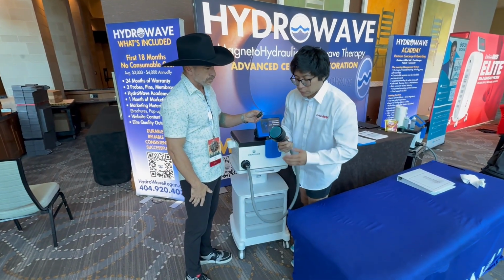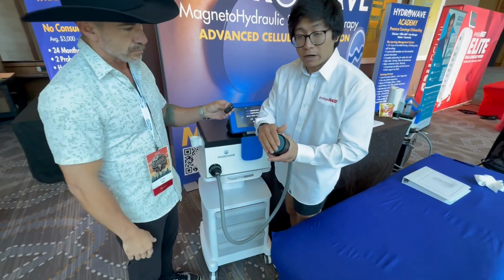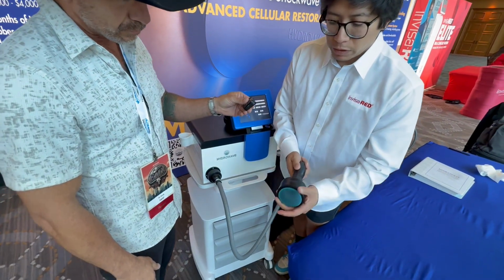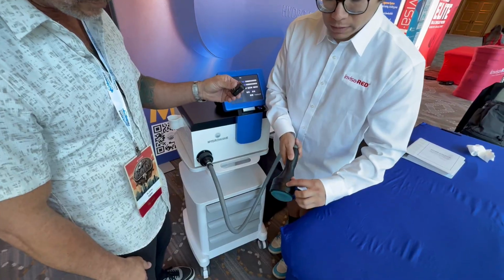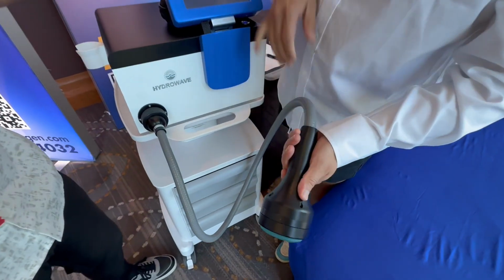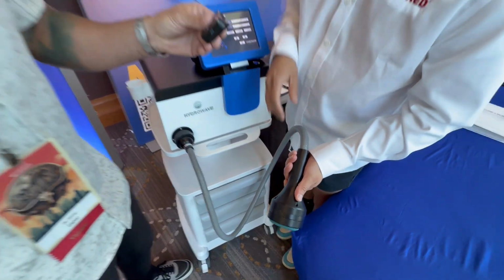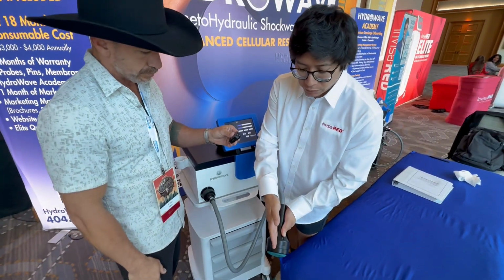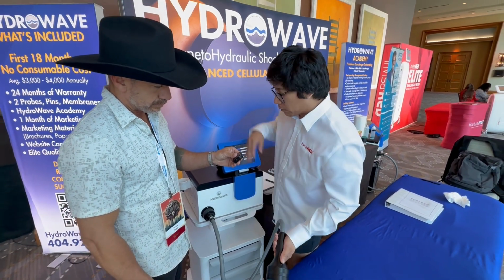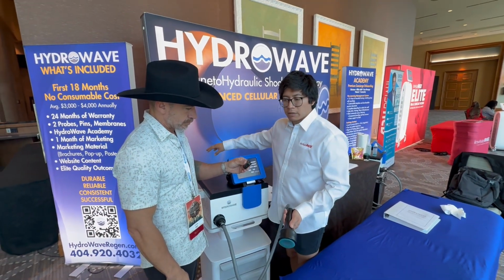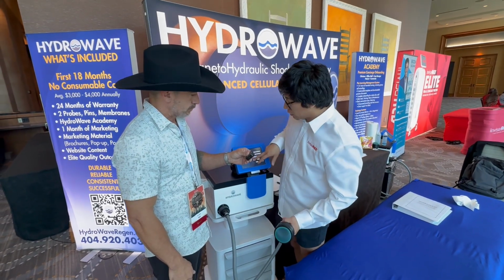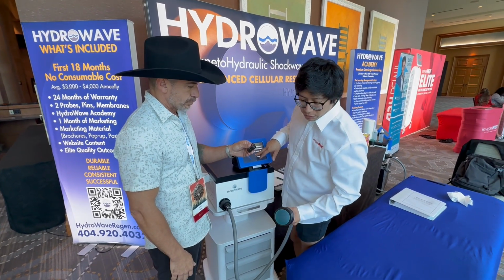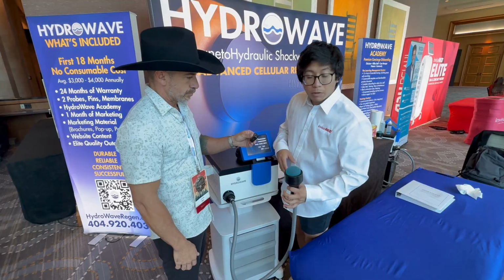If, let's say, for some reason there is air still in here, all you're going to do is tilt it at a 45-degree angle, with this little dot right here facing up, and then just click drain head. What that's going to do is have all those air bubbles go through the outlet port and out through the exit side. That way there are no air bubbles inside, and then you can just continue to fill it. Once the air bubbles are gone, you can continue to fill, and there are no air bubbles in there.